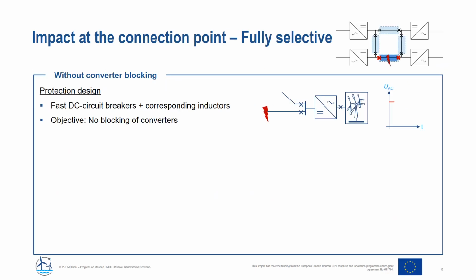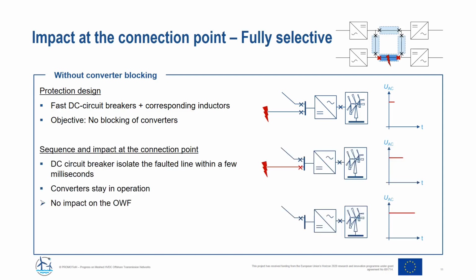The first protection design presented here is a fully selective protection design with fast DC circuit breakers and corresponding inductors at each line end and based on half-bridge MMCs. The objective of the protection system design is that no blocking of the converters takes place. So during fault clearing, DC circuit breakers isolate the faulted line within a few milliseconds. The converters stay in operation and there's no impact on the offshore wind farm so that the power flow can be resumed quickly.